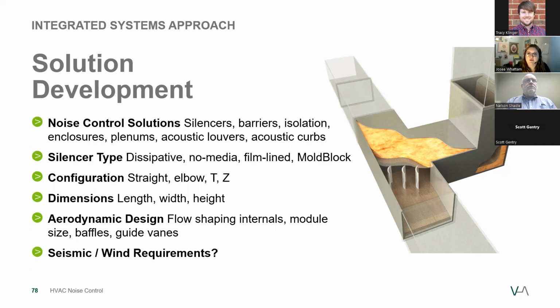Potential solutions can be developed using silencers, barriers, isolation, enclosures, plenums, acoustic louvers, and acoustic curbs. The media within a noise control product can be dissipative, no media, film lined, or MoldBlock. There are many different configurations possible, such as straight, elbow, T-shaped, Z-shaped, or suited to any possible site conditions. And the aerodynamic features of the noise control products can have flow shaping channels, various modules and baffle sizes, and guiding vanes. And finally, the wind and seismic restraints would always be considered. Remember though, effective noise control is a process, not a product.